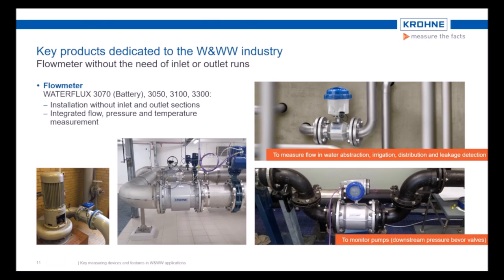Another application in which pressure is mandatory is to monitor pumps and valves in a water supply network. So normally you have two pressure transmitters to measure the pre-pressure and the back pressure of a valve, which is behind the pump, for example. This is important because behind the valve there are perhaps 10 bar because of the geodetic pressure, depending on the type of network behind. In front of the valve there is perhaps only 1 bar. So if the valve now opens, there would be a backflow through the pump, which may damage the pump. Therefore, the pump is pumping against the closed valve until the pre and the post pressure before and behind the valve are approximately the same, and then opens the valve only to ensure a flow in the right direction.